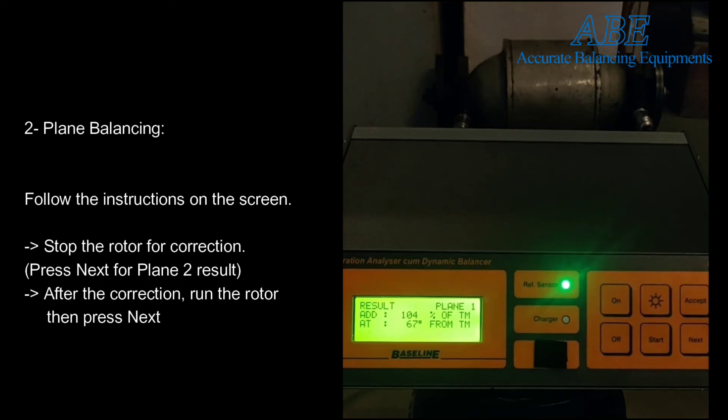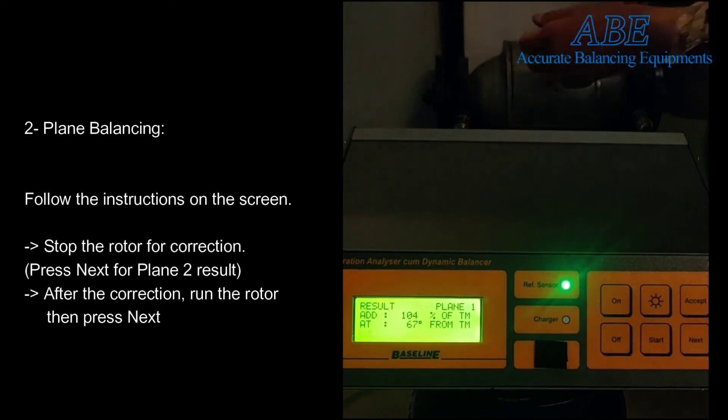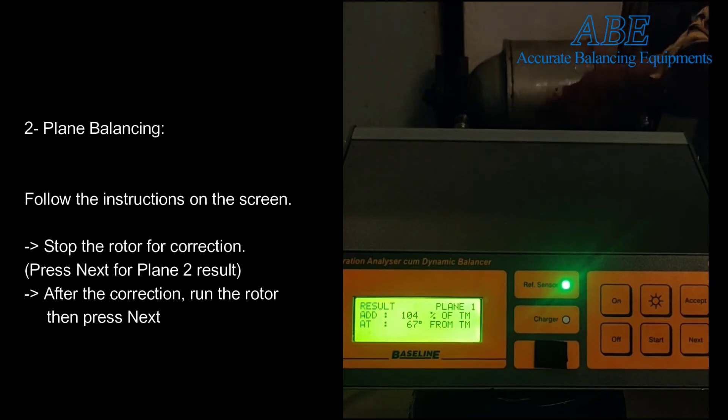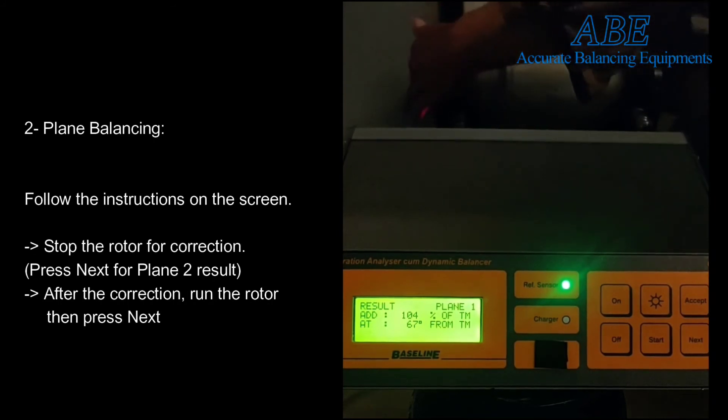Once the result comes, stop the rotor for the correction. In this case, for plane 1, the instrument is indicating that you need to add a weight that is 104% of the trial mass, and it is to be added at a position in the increasing direction, 67 degrees from the trial mass.